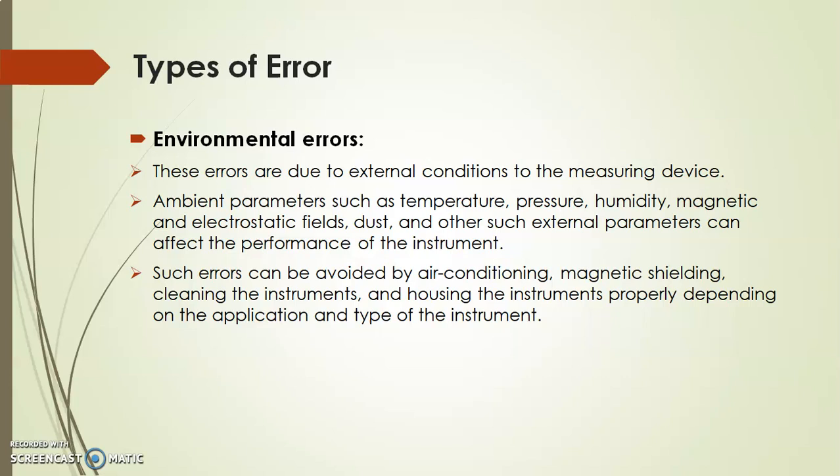The next systematic error is Environmental Error. These errors are due to external conditions affecting the measuring device. Ambient parameters such as temperature, pressure, humidity, magnetic and electrostatic fields, and dust can affect the performance of an instrument, causing environmental errors. Such errors can be avoided by air conditioning, magnetic shielding, cleaning the instrument, and housing it properly depending on the application and type of instrument.